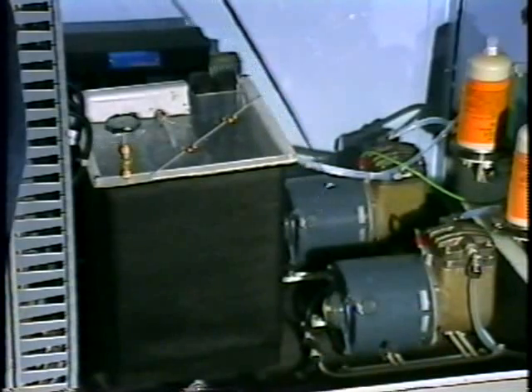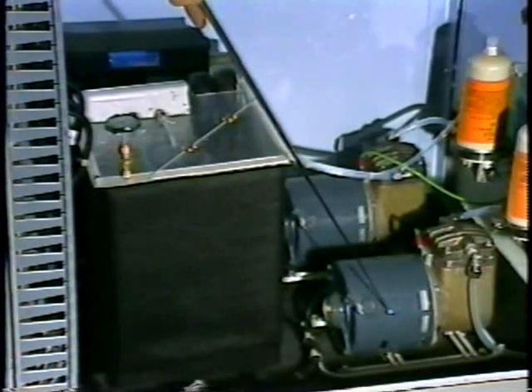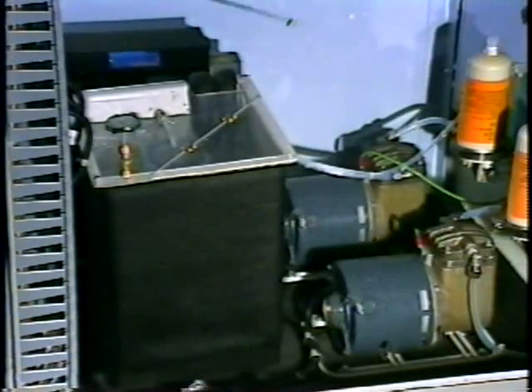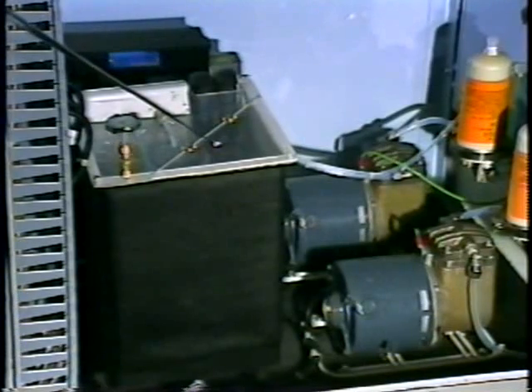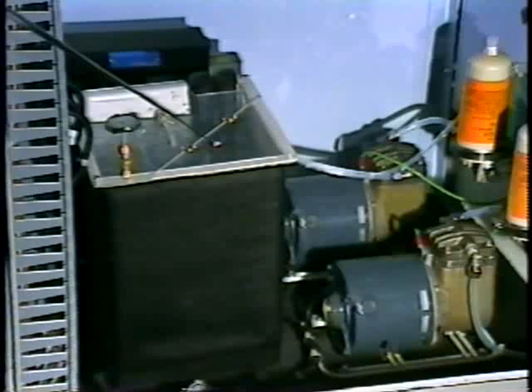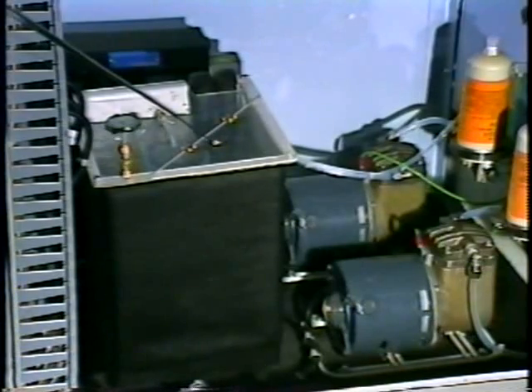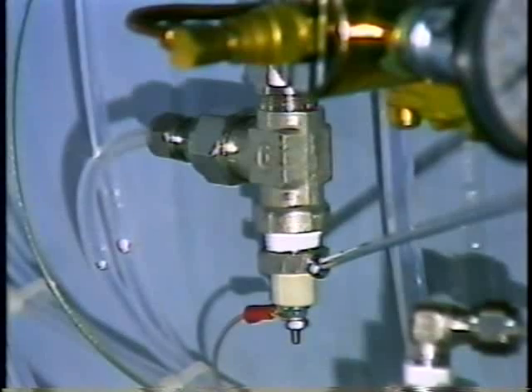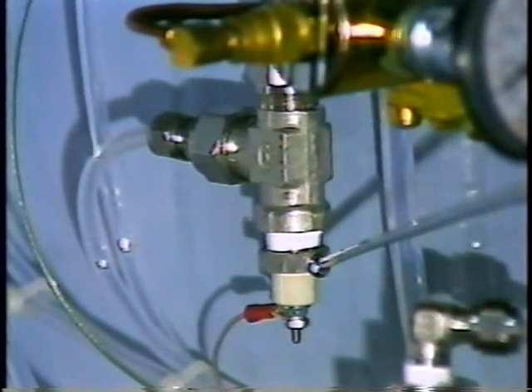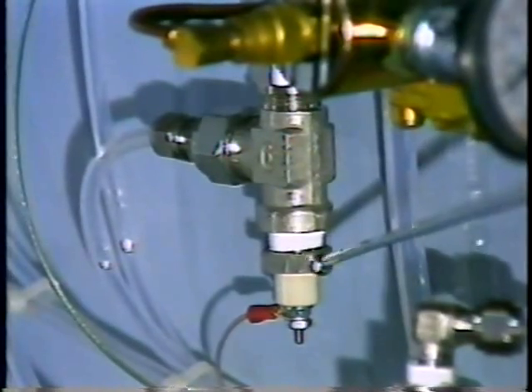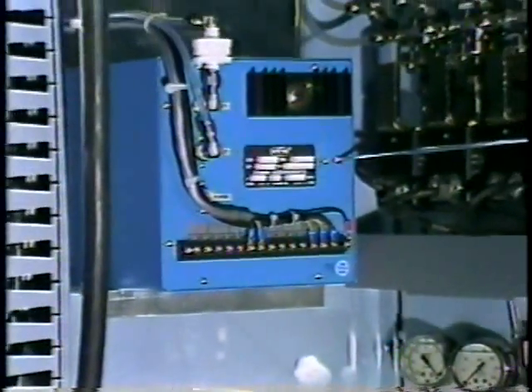The main sample pump and the bypass pump are simple diaphragm pumps for long and continuous operation. The refrigerated condenser chills the gas to remove all moisture above a dew point of 35 degrees Fahrenheit. This ensures that the analyzer sees only clean, dry gas. The conductivity sensor is a fail-safe mechanism. If it detects moisture in the gas stream, it will shut down the sample pump, thereby protecting the analyzer.